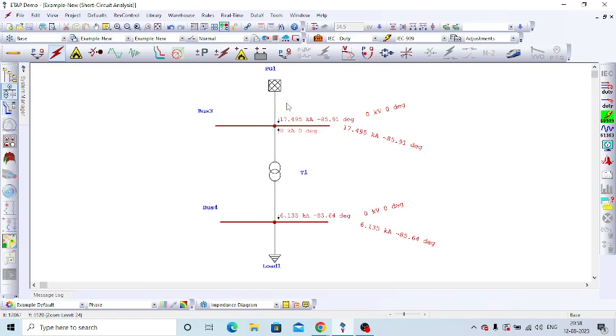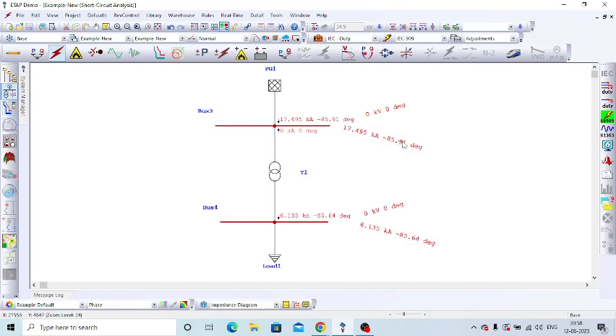Okay. So from the grid, we are getting 17.495 kilo ampere as a fault current during the fault. So in the bus, we are getting 17.495 kilo ampere at this bus. So in the low voltage side, in the 11 kV side, due to the transformer impedance, the fault current at the low voltage bus has been reduced. So it is 6.135 kilo ampere. So in the bus also it is 6.135 kilo ampere.